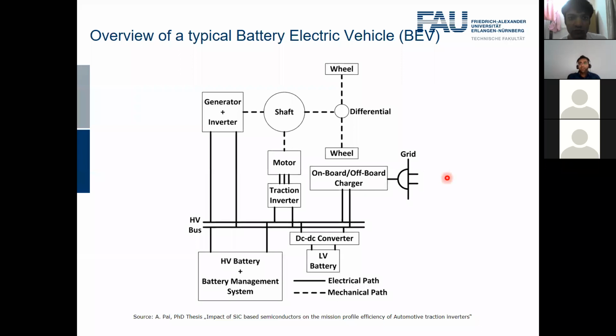We are not permitted by law to inject harmonics back into the grid. In Germany, for example, there is the BDEW Richtlinie, which regulates the limit of harmonics on the current on the grid side. So we need to install a filter on this side of the onboard charger. The onboard charger typically has filters on both the input and output side, but the traction inverter has filters only on the input side. I think this answers your first question.